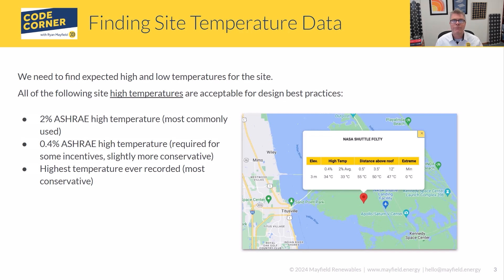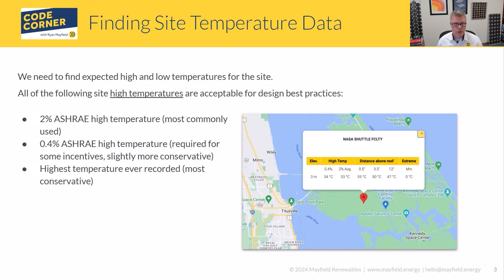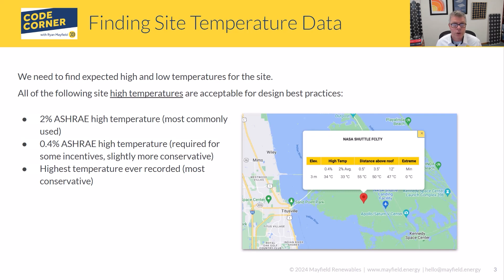Conversely, you have the 0.4% value. That value is greater than the 2% value because it's saying 99.6% of the time the temperature does not go above this. Either one is fine to use; the 2% value is what industry is standardized on and is a good number you should use. If you don't have somebody telling you to use a different number, that's what we use when we're doing the calculations. And then finally, you could use the highest temperature ever recorded — very conservative. You will just be much more restrictive on what your results are going to be, but that's going to be the most conservative option.